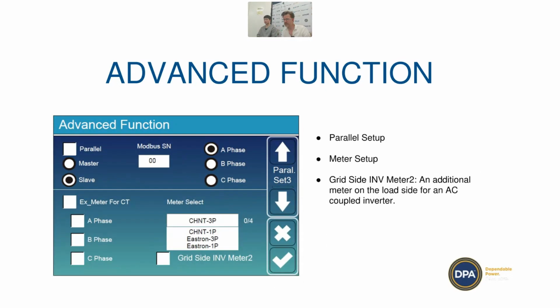The second page of advanced function - up the top you've got parallel master slave, and then phases A, B, and C. If you're doing single phase with just a single inverter, it is slave, not master - a bit counterintuitive, but that's how it comes as standard. If you're doing parallel or three-phase, you're going to click parallel, and designate one as the master set to phase A, the subsequent one as slave and B, and the third as slave and C. You'll set each one with a different Modbus address as well.